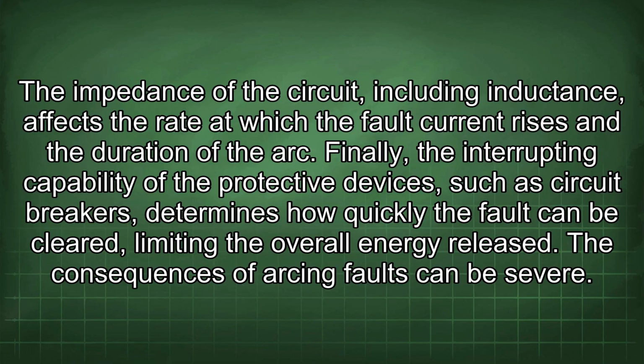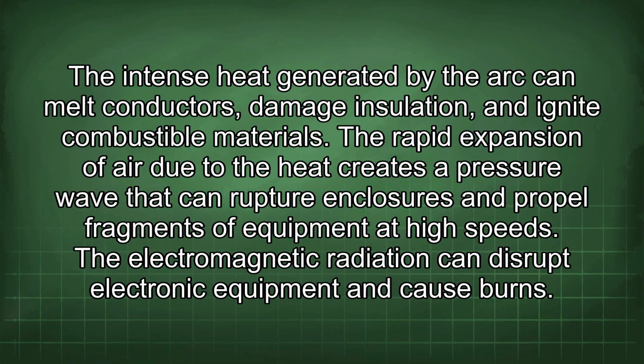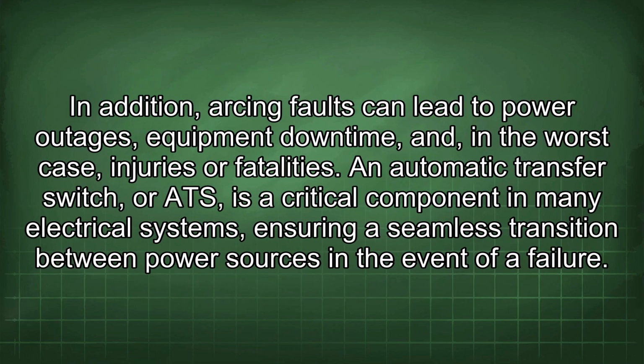The consequences of arcing faults can be severe. The intense heat generated by the arc can melt conductors, damage insulation, and ignite combustible materials. The rapid expansion of air due to the heat creates a pressure wave that can rupture enclosures and propel fragments of equipment at high speeds. The electromagnetic radiation can disrupt electronic equipment and cause burns. In addition, arcing faults can lead to power outages, equipment downtime, and, in the worst case, injuries or fatalities.